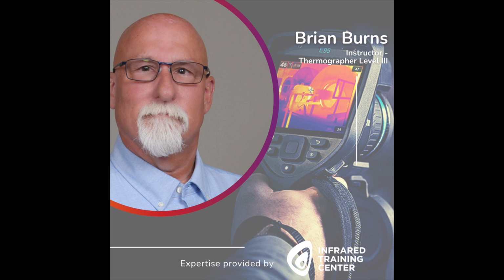Now, what are the conditions that the International Electrotechnical Commission, which we know as the IEC, specifies to give us the ideal monitoring conditions when we do the inspection? What we really are looking for is better than 600 watts per square meter. This is the actual amount of radiant energy coming from the sun to the panel. Anything less than that, the panels are not loaded enough. So early in the morning, probably not loaded enough, or just before sunset, not loaded enough.